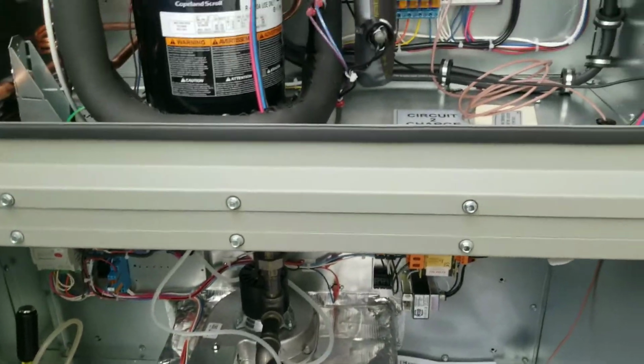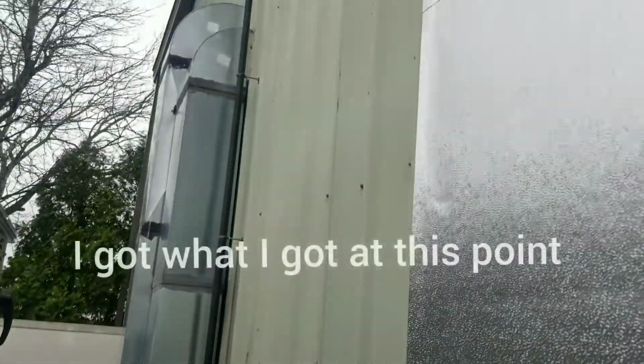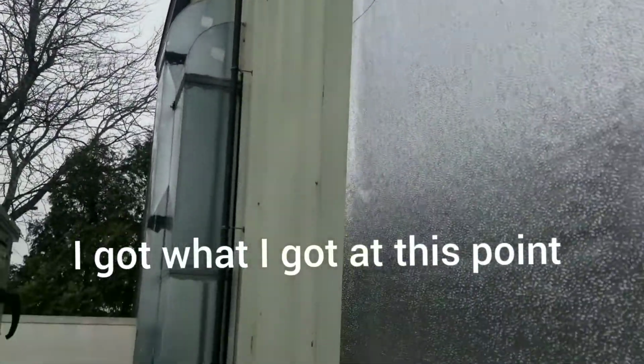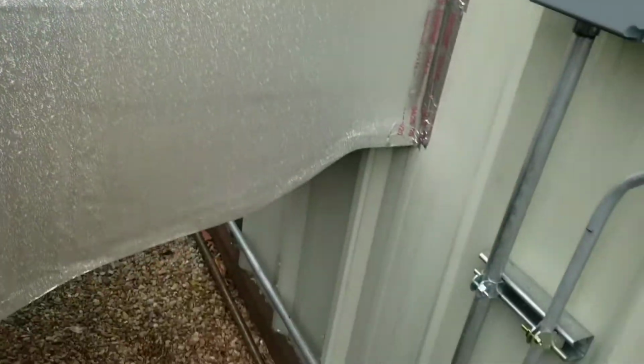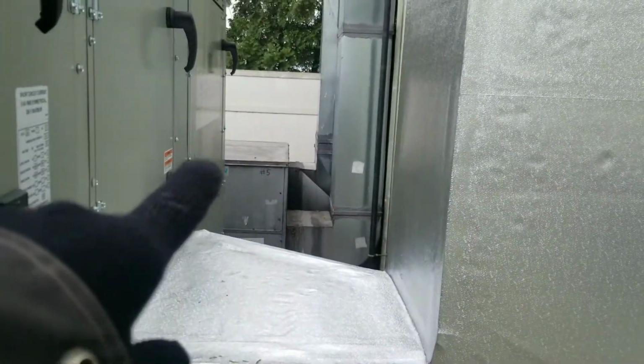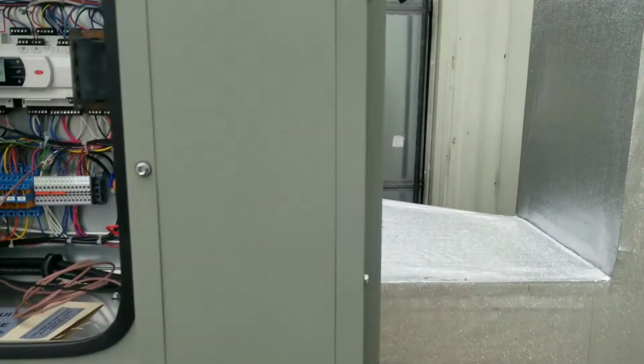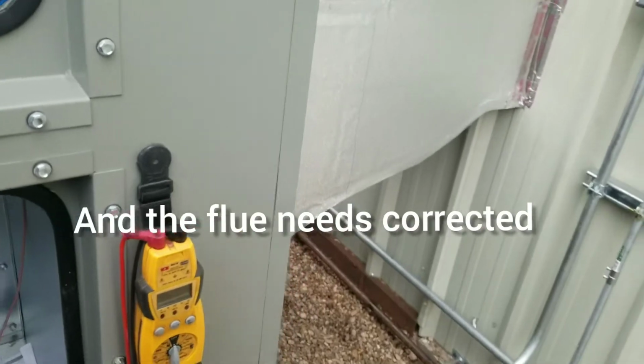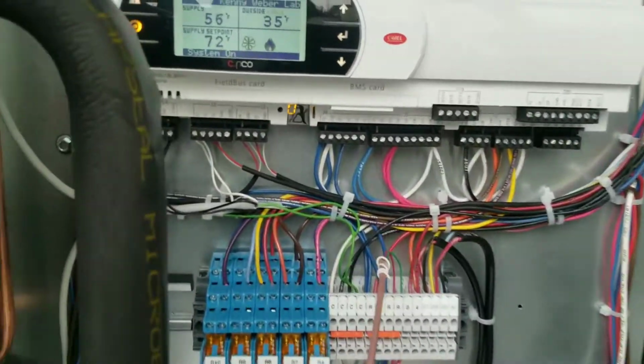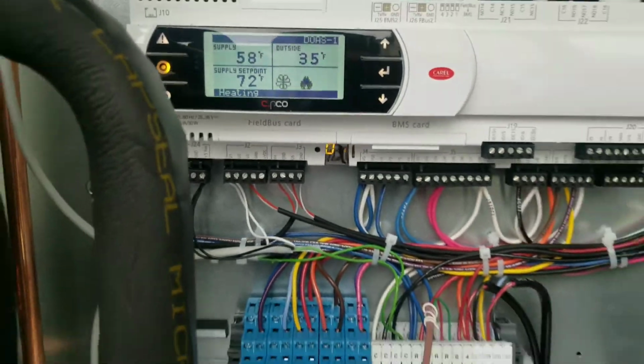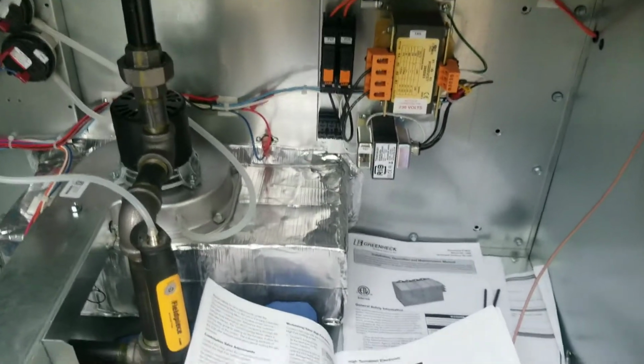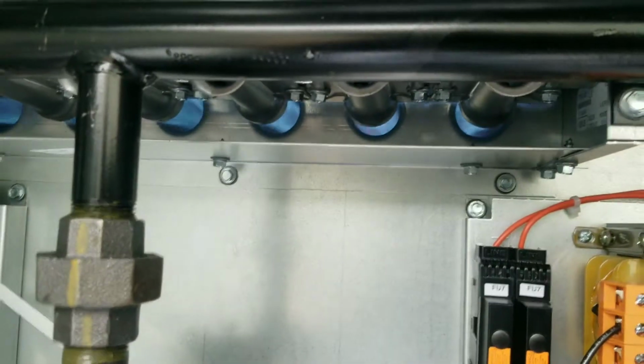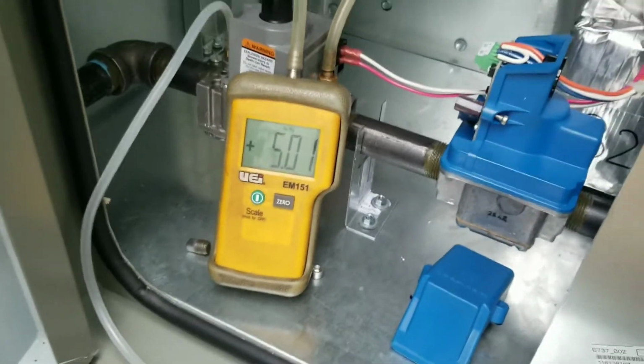We'll have to investigate the gas line. I don't have a regulator out here that I can adjust. It goes into the building, so it's low pressure gas. We may have to increase the pressure a little bit. I had to shut that guy off because it fired and it was affecting my gas pressure over here. So that's going to be a problem for another day. So now we're out of our commissioning mode. Normal operation at 56-degree supply temp. We're in high fire right now. 3.5 water column. Burner looks good. I got 5 inches coming out.